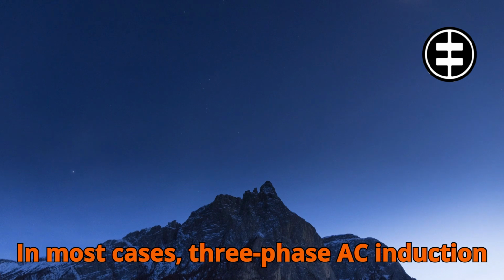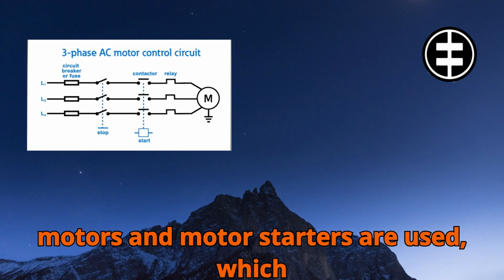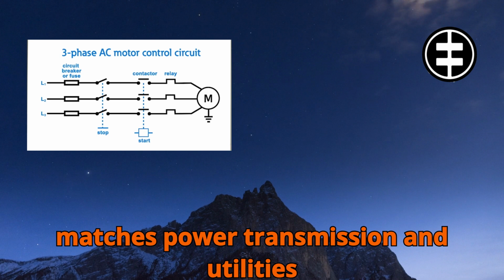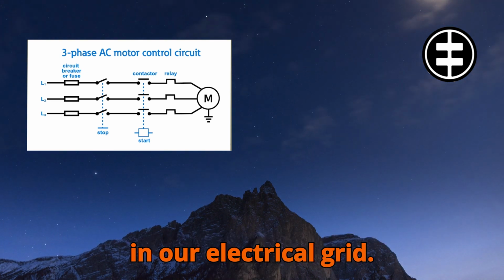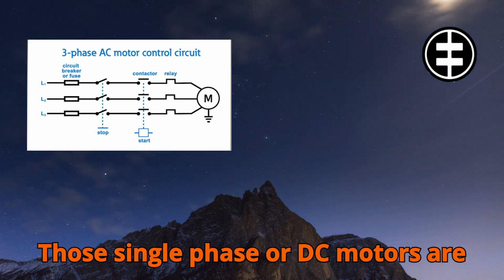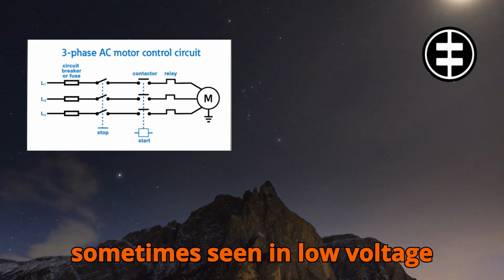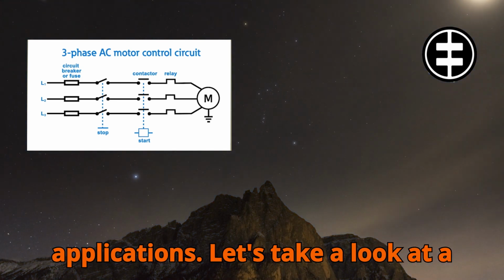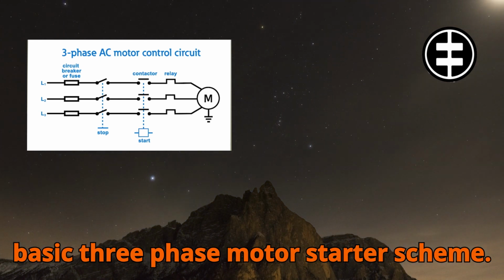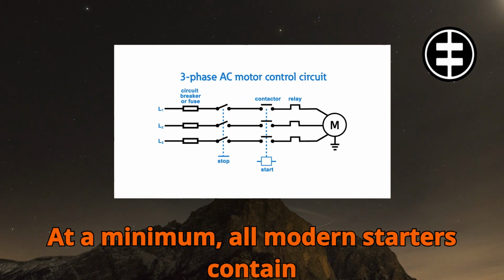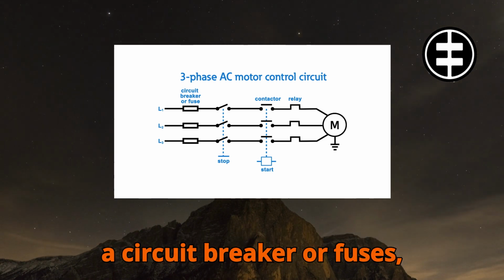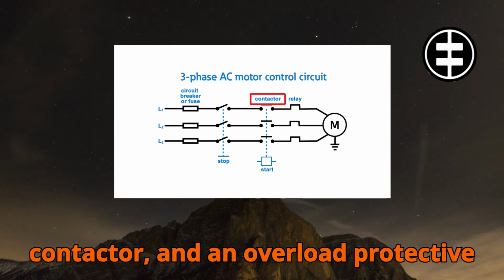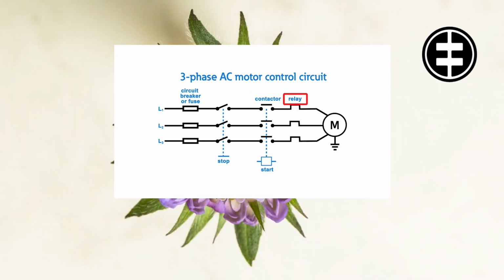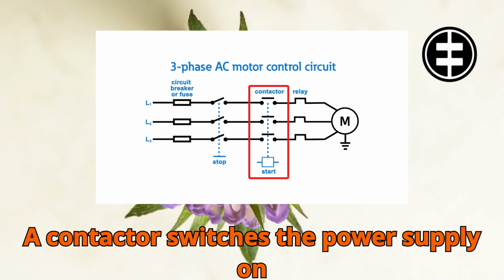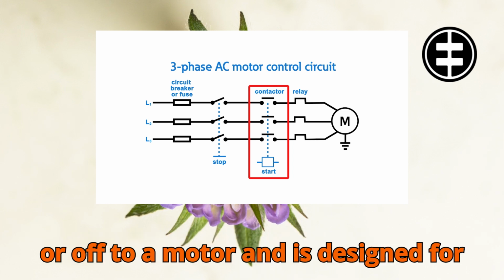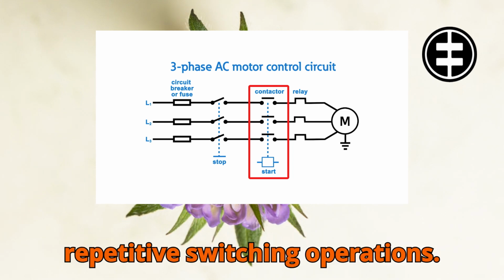In most cases, three-phase AC induction motors and motor starters are used, which matches power transmission and utilities in our electrical grid. Though single-phase or DC motors are sometimes seen in low-voltage applications, let's take a look at a basic three-phase motor starter scheme. At a minimum, all modern starters contain a circuit breaker or fuses, contactor, and an overload protective relay.